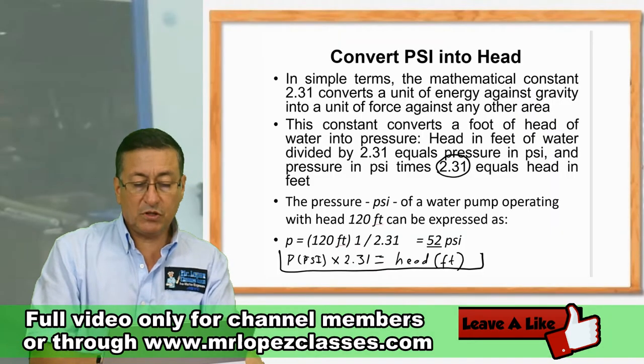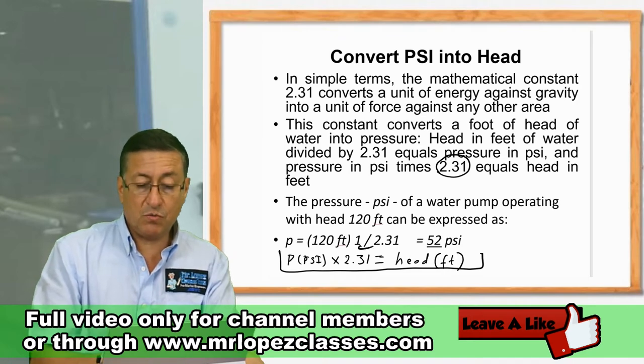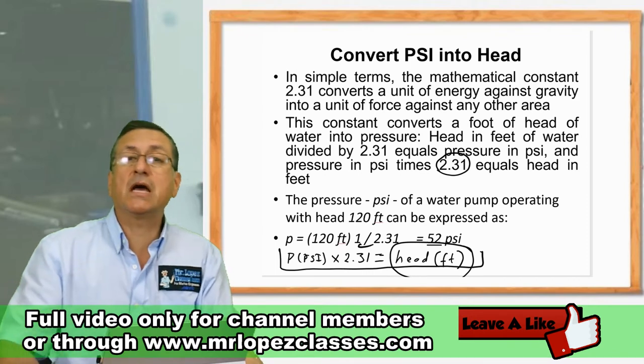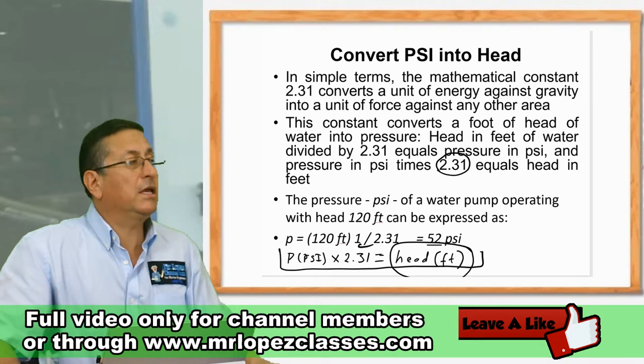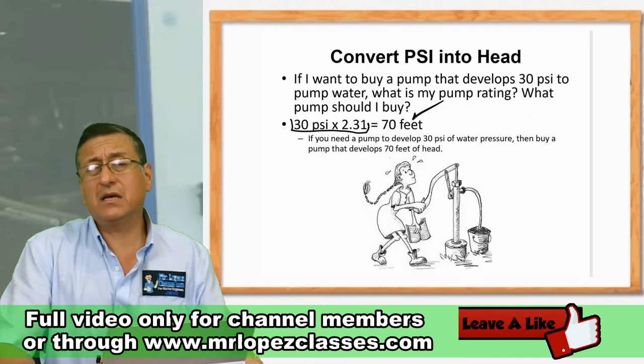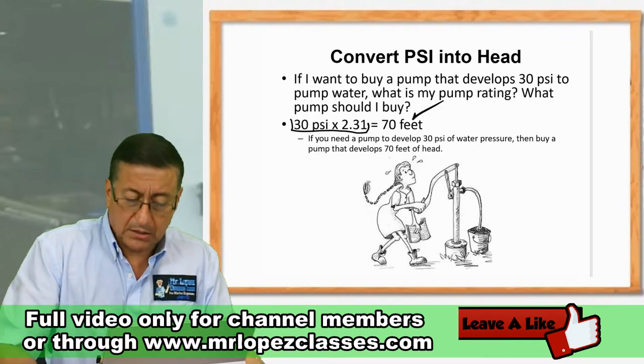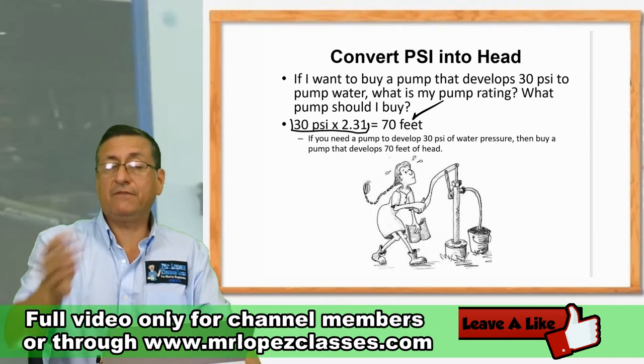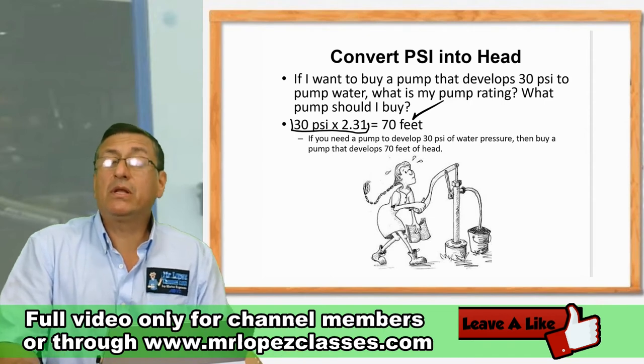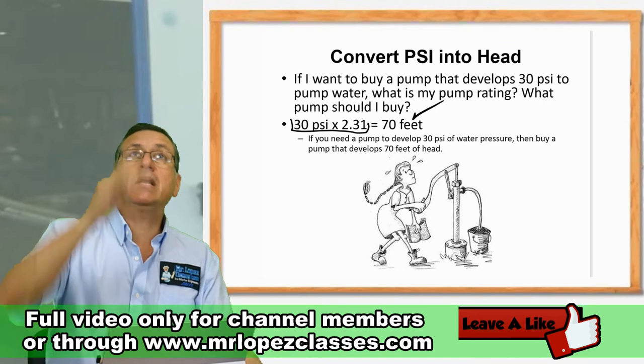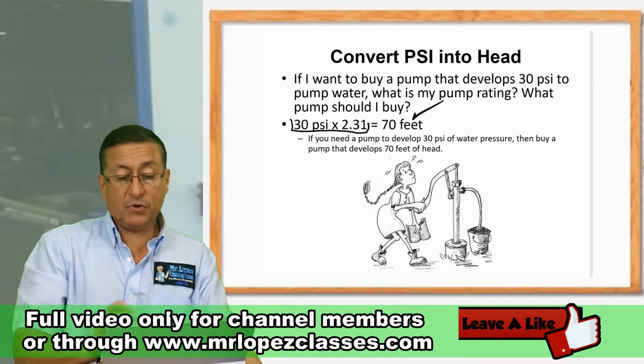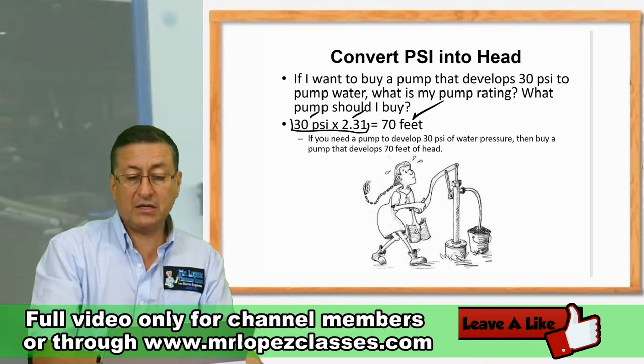The formula is simple: if you multiply the PSI times 2.31, that gives you the head of the pump. The head equals pressure times 2.31. For example, if I have a pump of 30 PSI, the maximum distance the fluid can reach is 30 times 2.31, which equals 70 feet.